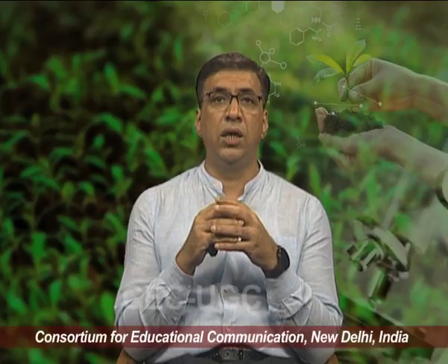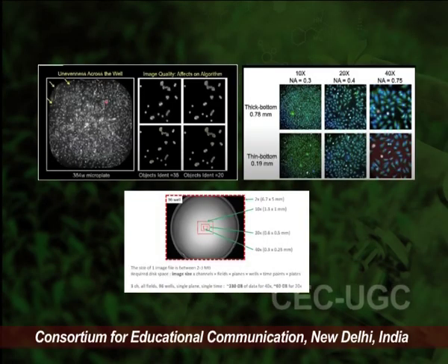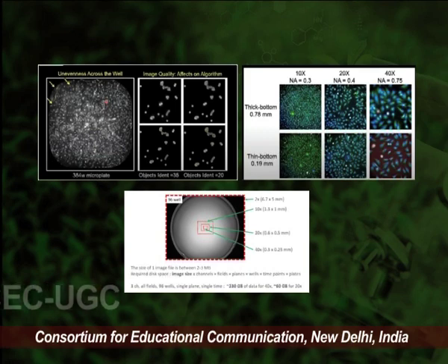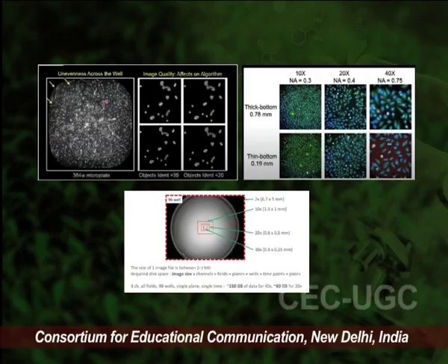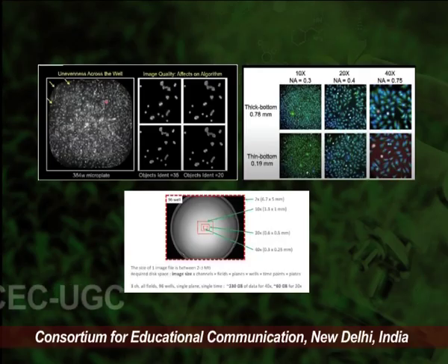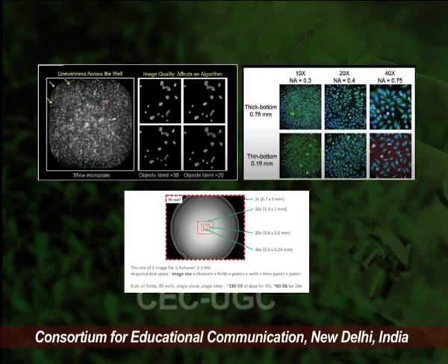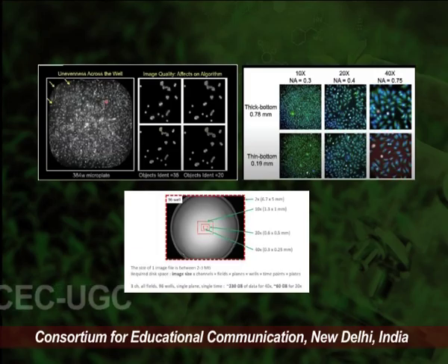Similarly, thickness of the cells also has an impact on the image. As you can see on the image on the right, the upper images were taken when we used a microplate having a bottom thickness of 0.7 millimeter, and on the lower side we have a 0.19 millimeter thickness of the well base. So you can clearly see that the image at the highest magnification, that is 40x, is slightly blur when we are using more thickened base microplates in comparison to the thin plates.